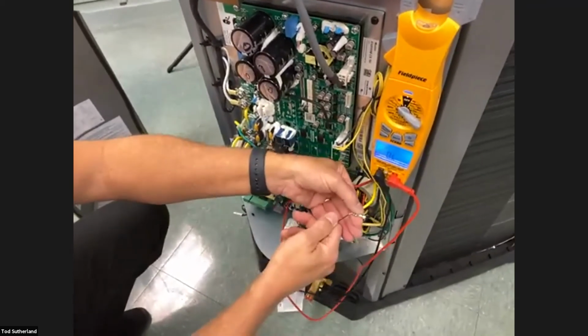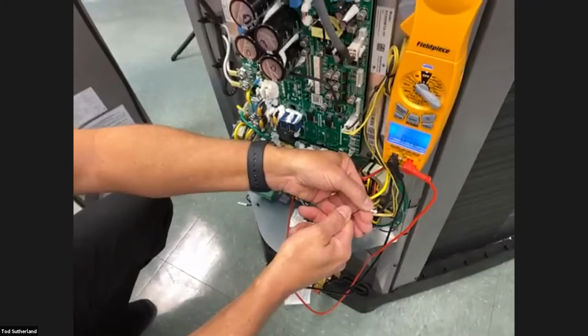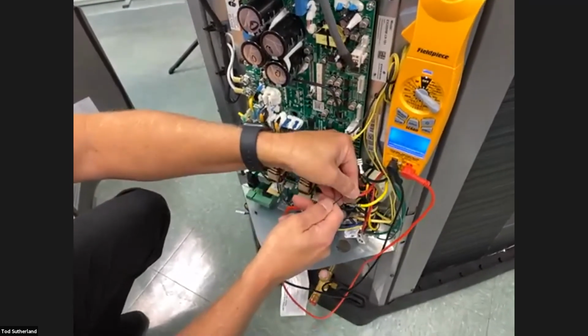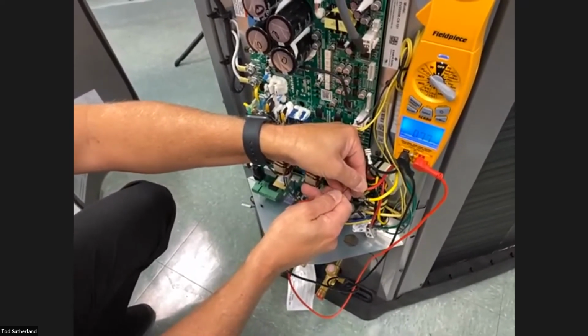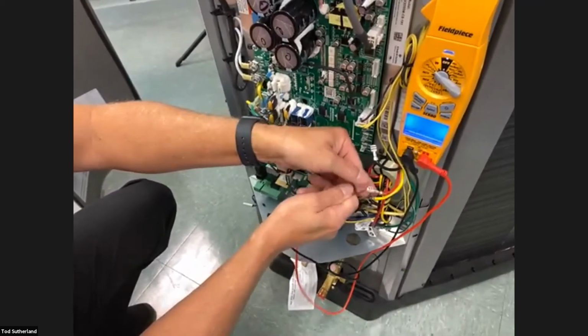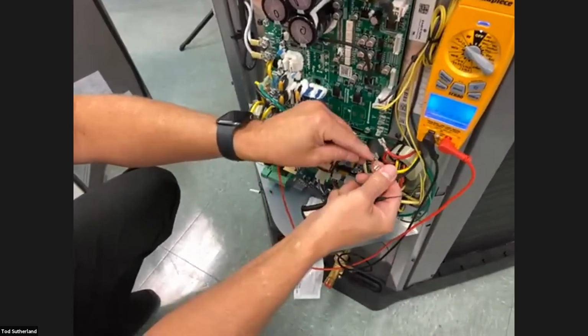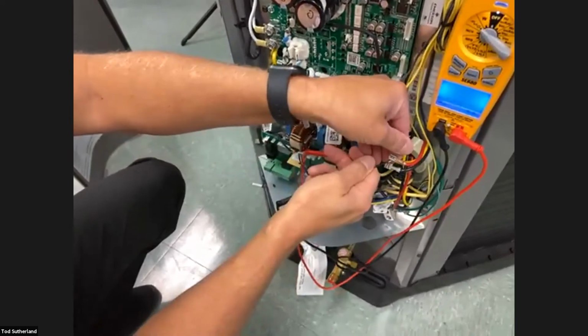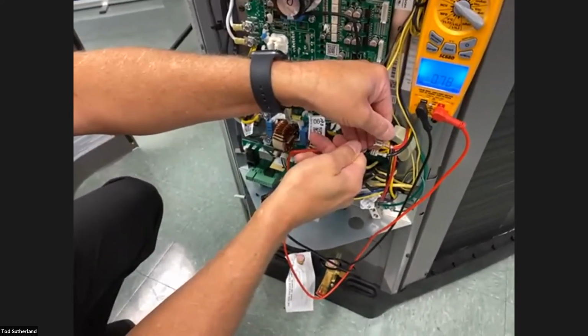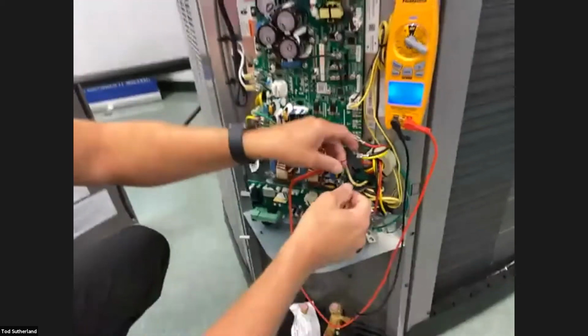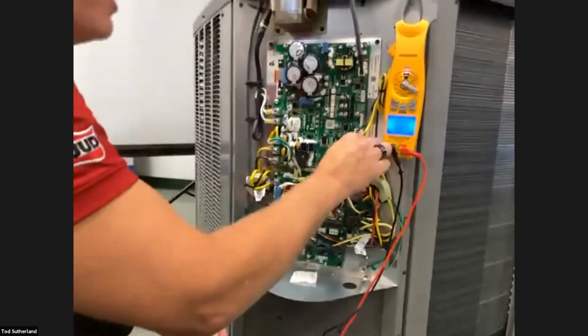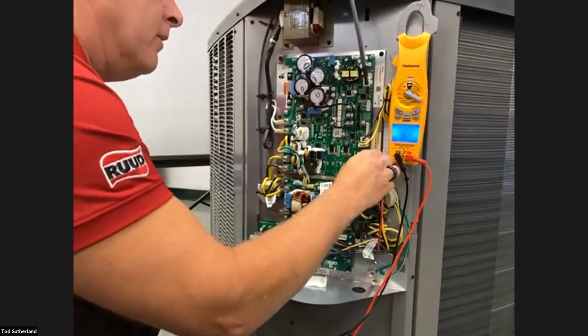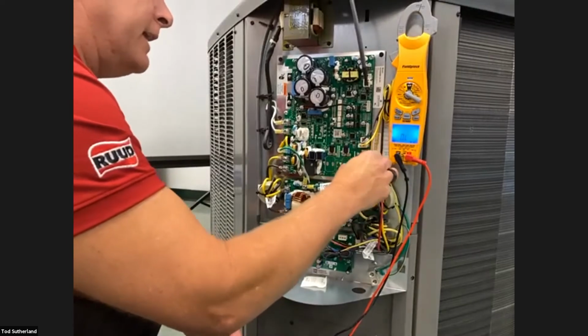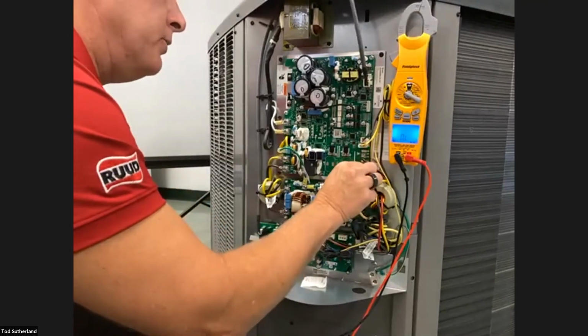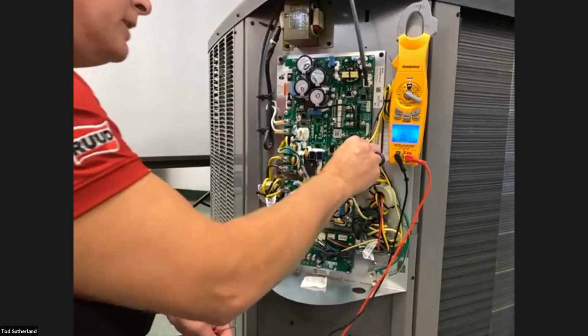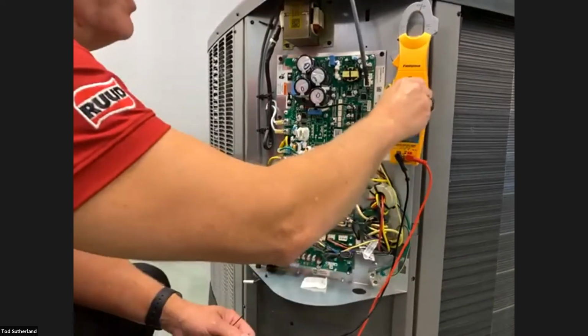All right, let me get these in here. 0.76, 0.77, and then we want to go from black to red, should be the same. 0.78. So as long as they're all close in range like that, then your compressor is ohmed out just fine. And just like any other compressor, you can also check at the ground by checking from each one of the wires to a piece of the copper tubing inside to make sure that you're good there on your compressor.